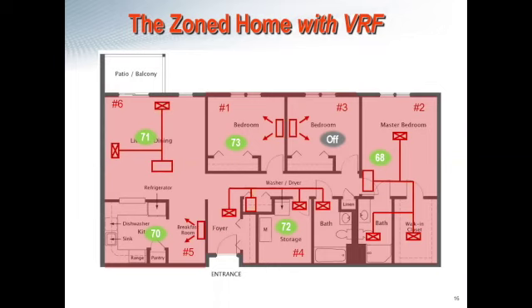But really what we're looking at here is that each of these individual zones is going to be working to its own set point and only providing a specified amount of heating or cooling. That's really the main takeaway for VRF technology in general: its efficiency through zoning. So we always want to think about how many independent zones we can service, because we want to only serve the zones that are going to be most prominently used while turning off the zones that are not going to be used or rarely used. That's what we're talking about when we're talking about diversity.